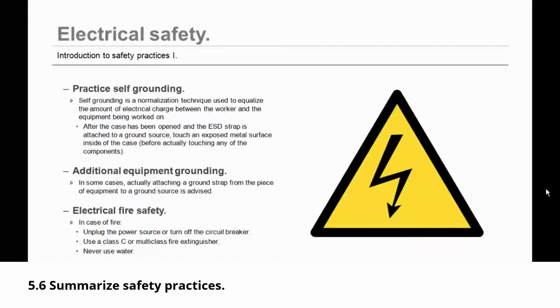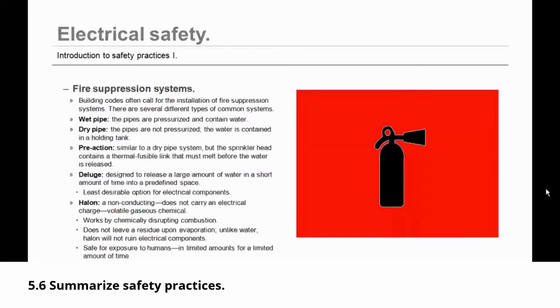In case of an electrical fire, unplug the power source or turn off the circuit breaker. Always use a Class C or multi-class fire extinguisher on electrical fires. Never use water. You run the risk of electrocution and damaging that equipment even more than the fire is already doing. So let's talk about fire suppression systems.